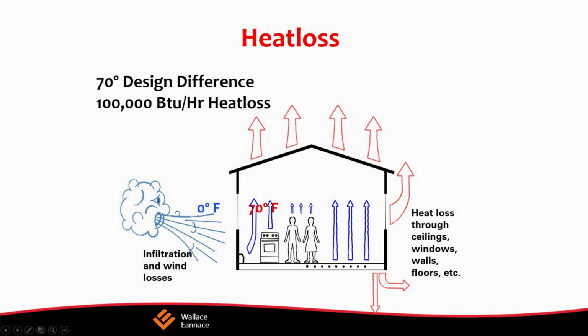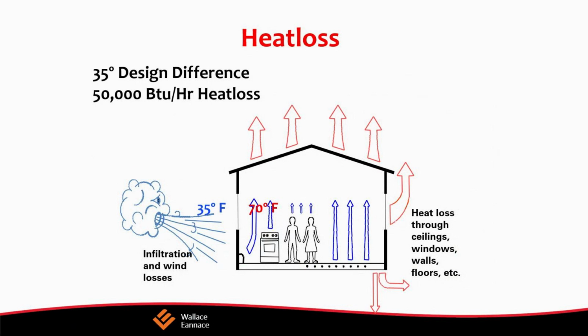So how do you do that? Well, you can put in smaller boilers, or you could put in less radiation. But if you put in smaller boilers with less radiation, what's going to happen? When you do hit those design conditions, those few hours, that 100 hours or so, it's going to be mighty cold. The better option is to lower the water temperature.